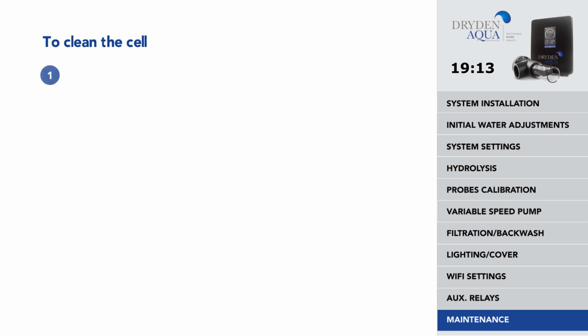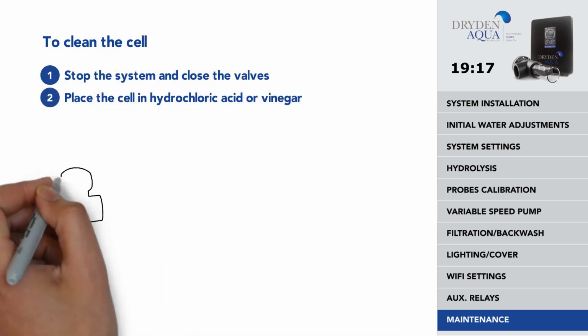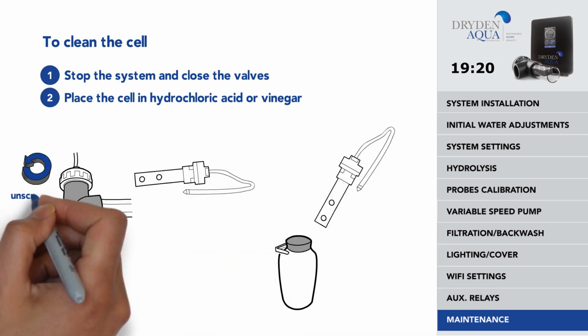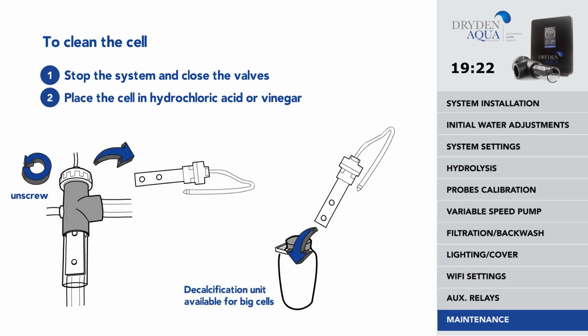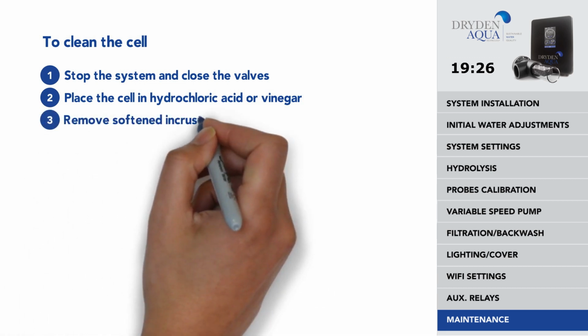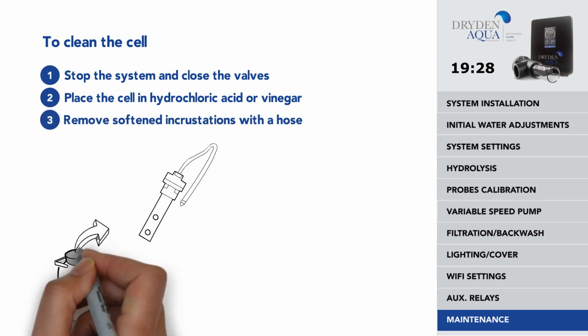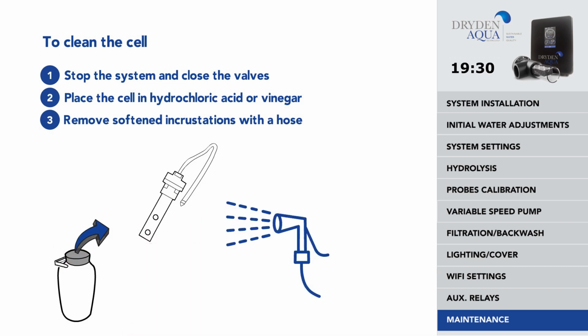To clean the cell, stop the system and close the valves. Place the cell for no more than 10 minutes in 3% hydrochloric acid or put it for 2 to 4 hours in normal vinegar. You may also use a high-pressure cleaner. Once the incrustations have softened, remove them with a hose.